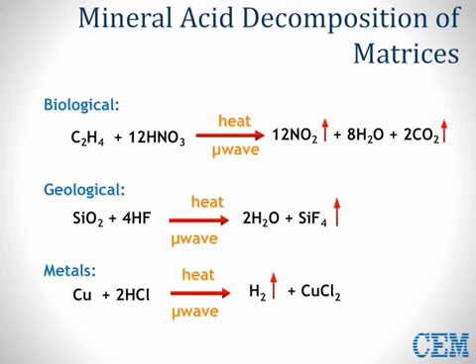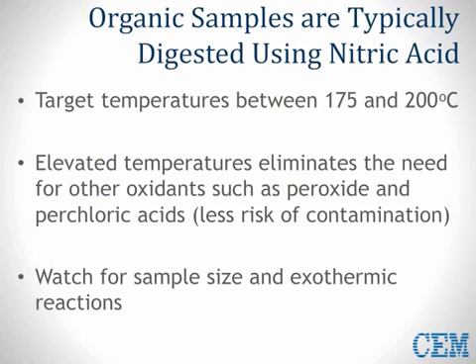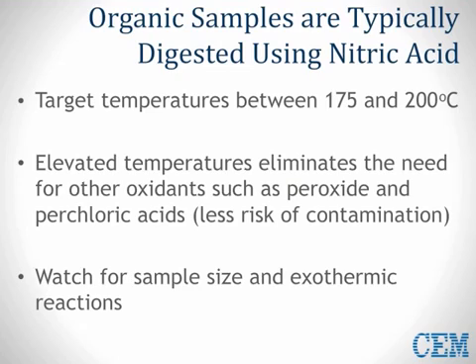When acids are heated in a microwave, they begin to break bonds, as shown in this diagram. The first reaction represents an organic reaction in which lots of carbon dioxide and nitrous oxide gases are released; vessels must be able to handle the production of these gases. The second and third reactions represent inorganic reactions which produce much less gas. Organic-based samples — those containing carbon, hydrogen, oxygen, and nitrogen — are typically digested in nitric acid alone at temperatures between 175 and 200 degrees Celsius. Since nitric acid is heated well above the boiling point, you can eliminate other oxidizing acids such as perchloric or hydrogen peroxide. The main concern is an exothermic reaction which generates a lot of gas quickly; sample size and the right method will help with this.